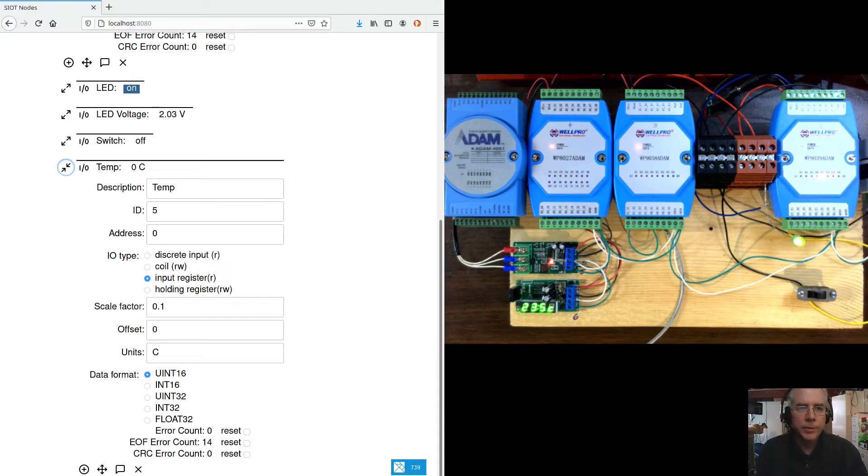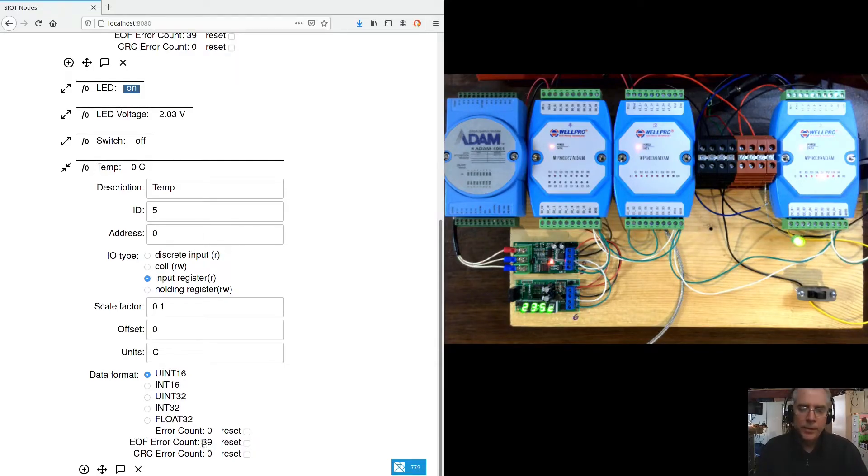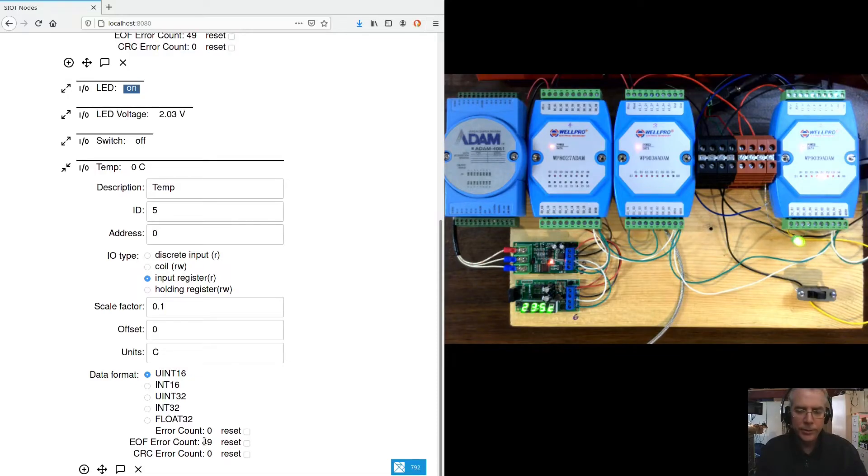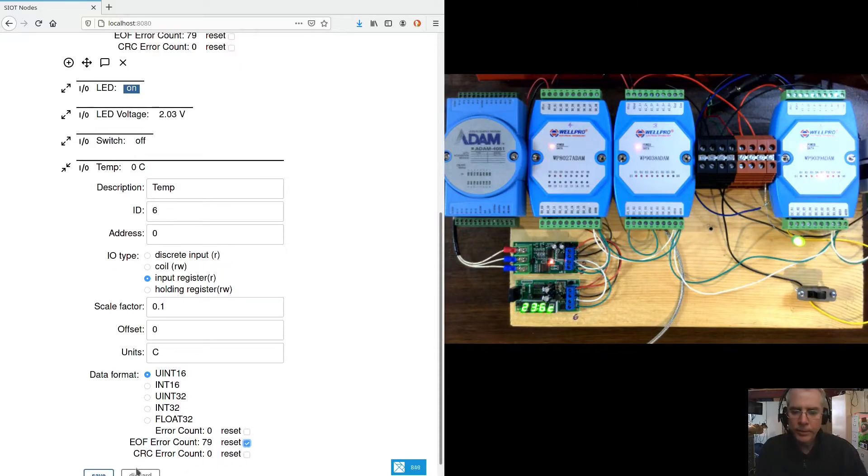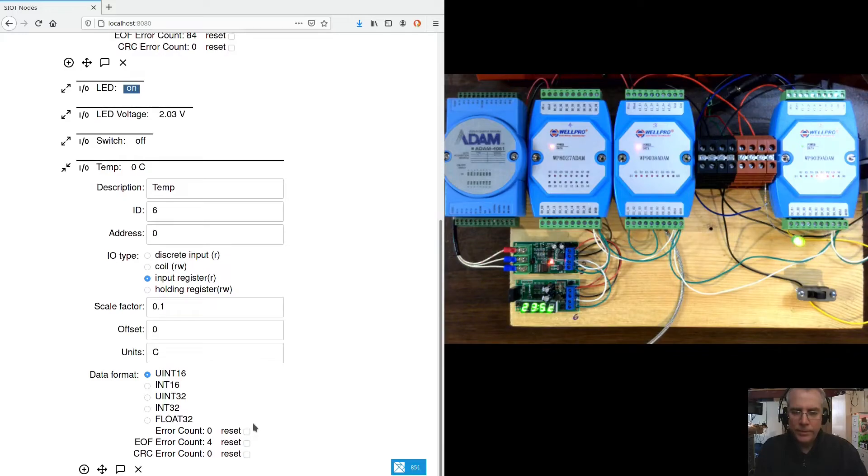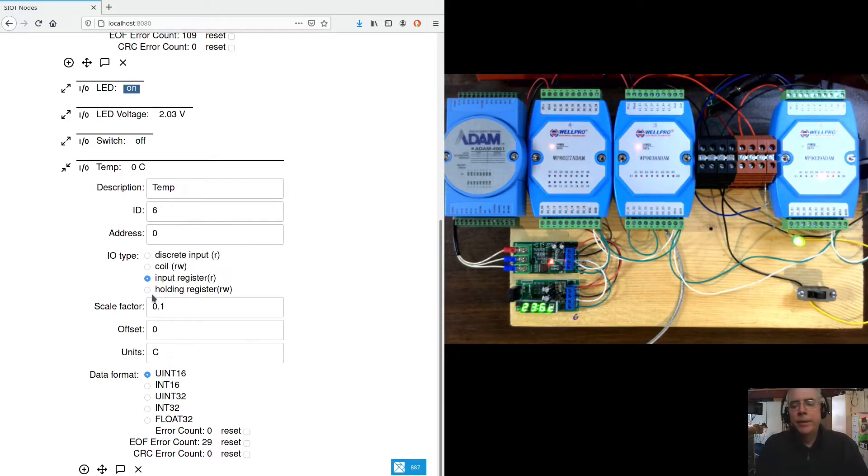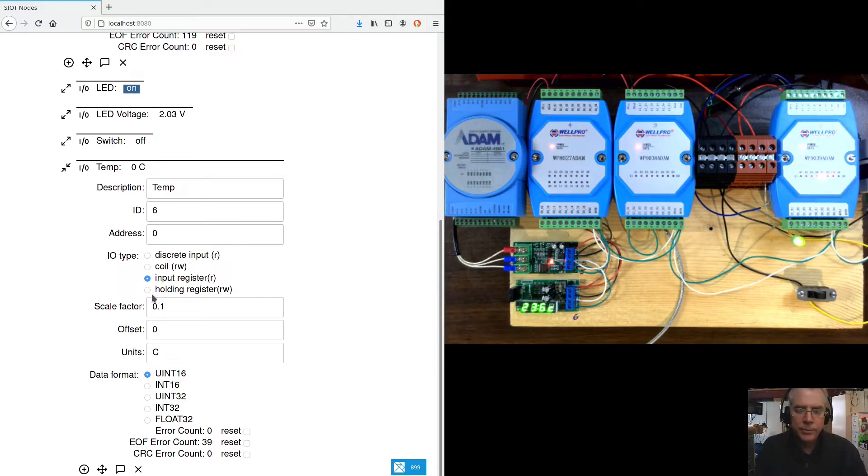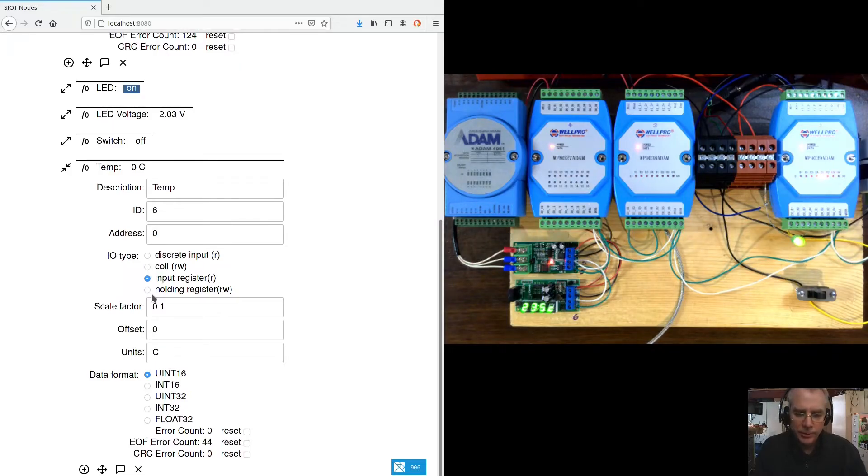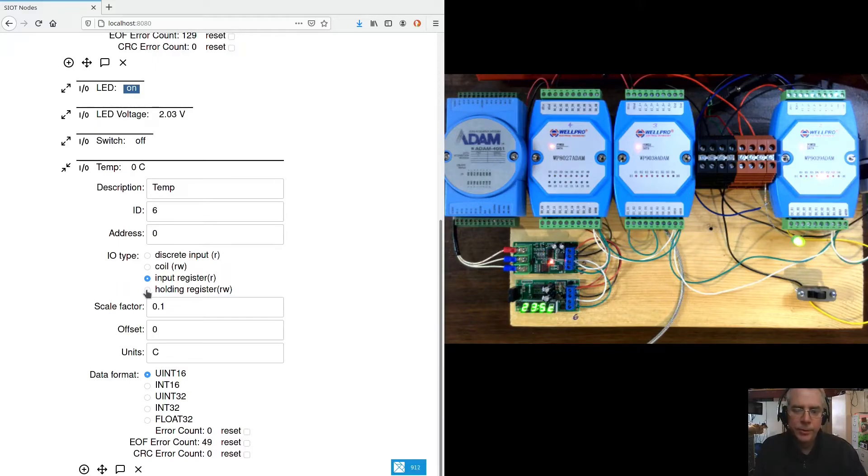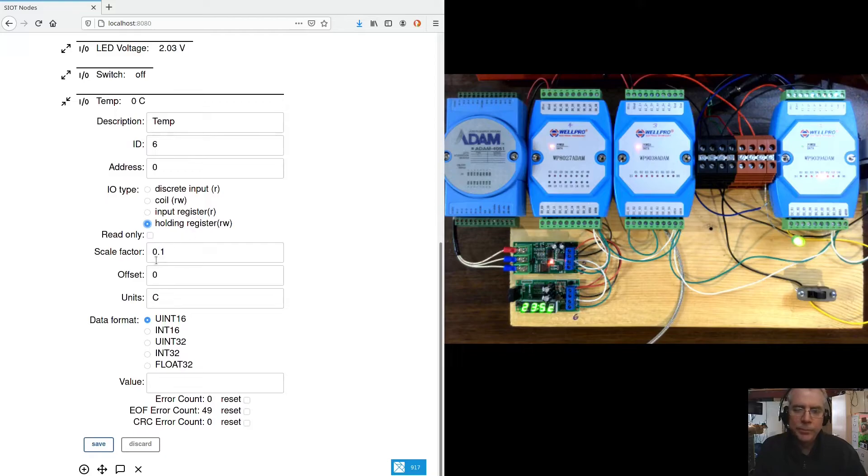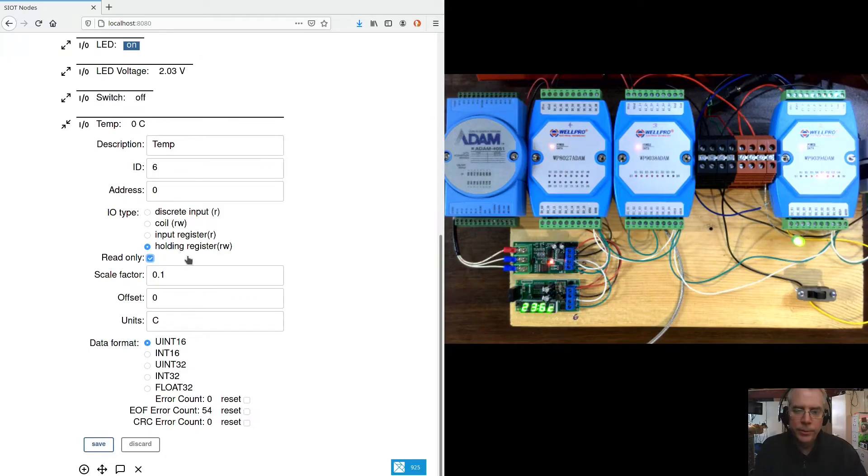This doesn't seem to be reading, so let's go back to our console. Now we notice down here there's an EOF, that's End of File Error Count. So that basically means the device isn't responding and we can see that it's continuing to increase. So any of these error counters we can just reset. Oh, I remember what's wrong with this. So this is kind of a strange device, but typically holding registers are registers you write in a device. But this particular device uses holding registers for read values, which isn't really typical. So what we did in Simple IoT, we added the ability to have a read-only holding register.